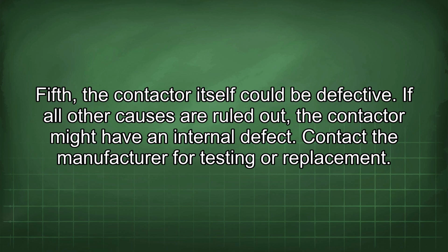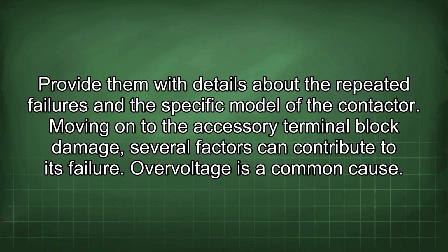Fifth, the contactor itself could be defective. If all other causes are ruled out, the contactor might have an internal defect. Contact the manufacturer for testing or replacement. Provide them with details about the repeated failures and the specific model of the contactor. Moving on to the accessory terminal block damage, several factors can contribute to its failure.